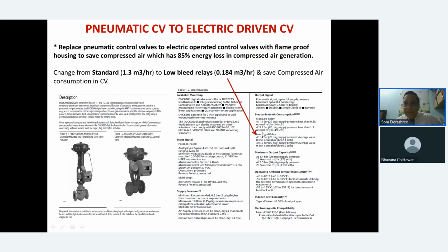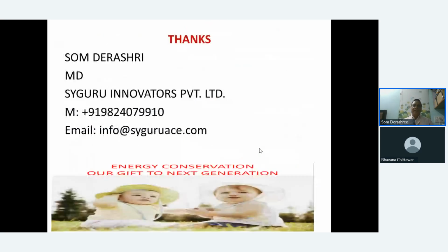So it has to feed this. Now they also have, in a catalog, a low bleed valve. At 5.5, it is only consuming 0.18. What is the difference? 1.3 against 0.18. A tremendous amount of saving is possible through that, and these are things that one has to look forward to. So with this, I end my presentation. And if there are any questions, I'll be happy to address them if possible.